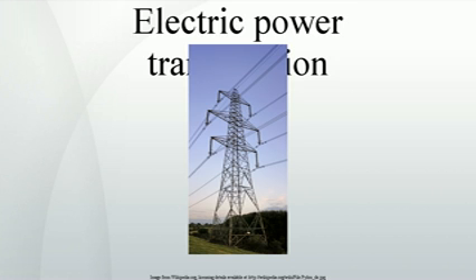Optical fibers can be included in the stranded conductors of a transmission line, in the overhead shield wires. These cables are known as optical ground wire, OPGW. Sometimes a stand-alone cable is used, all dielectric self-supporting, ADSS, cable, attached to the transmission line cross arms. Some jurisdictions, such as Minnesota, prohibit energy transmission companies from selling surplus communication bandwidth or acting as a telecommunications common carrier. Where the regulatory structure permits, the utility can sell capacity in extra dark fibers to a common carrier, providing another revenue stream. Electricity market reform.